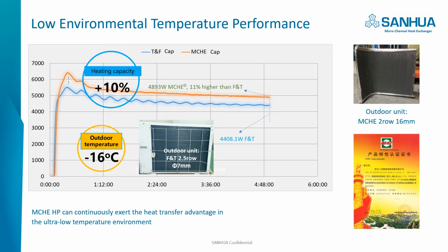And we recorded the capacity along the time. And we found that the microchannel heat exchanger and the fin tube heat exchanger both don't need defrosting even for 5 hours. And microchannel always keeps 11% higher capacity than the fin tube heat exchanger. So that means the microchannel heat pump can continuously exert the heat transfer advantage in the ultra-low temperature environment.